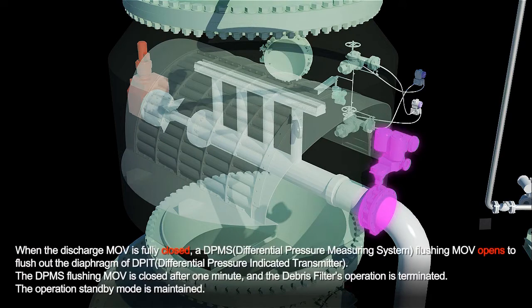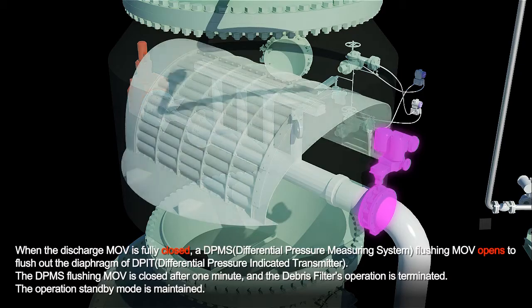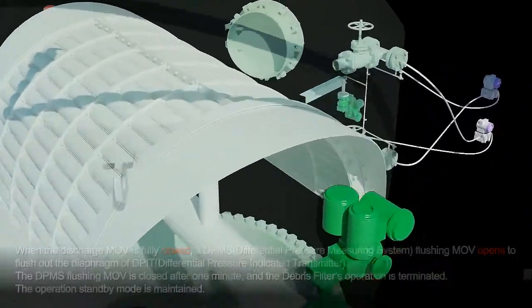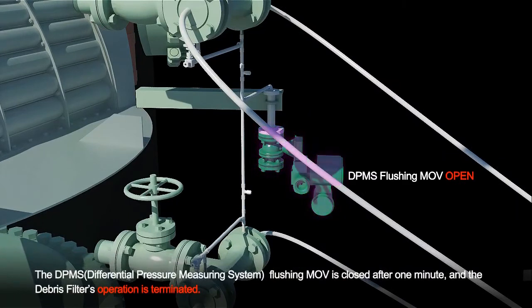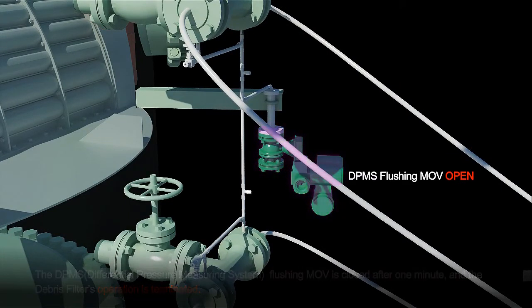When the discharge MOV is fully closed, a DP-MS flushing MOV opens to flush out the diaphragm of DP-IT. The DP-MS flushing MOV is closed after one minute and the debris filter's operation is terminated.